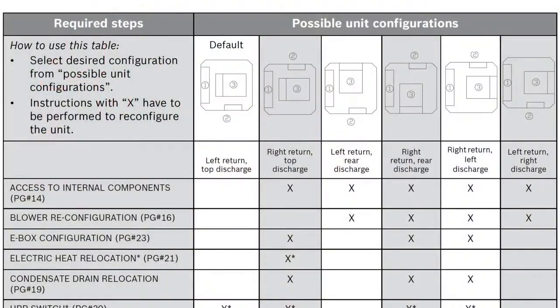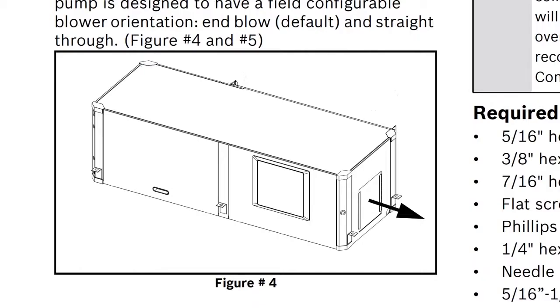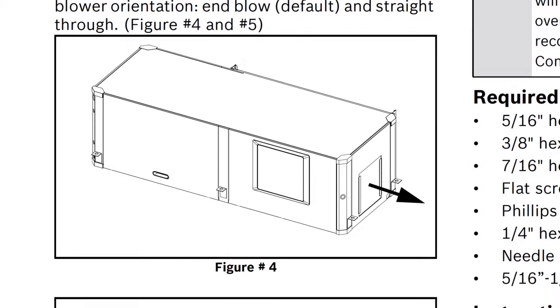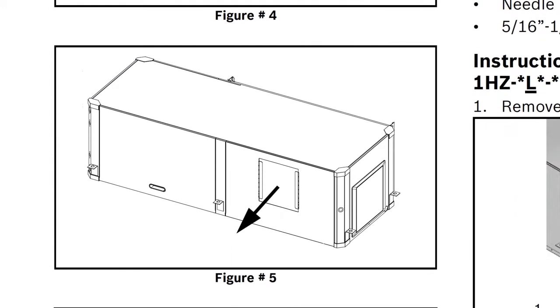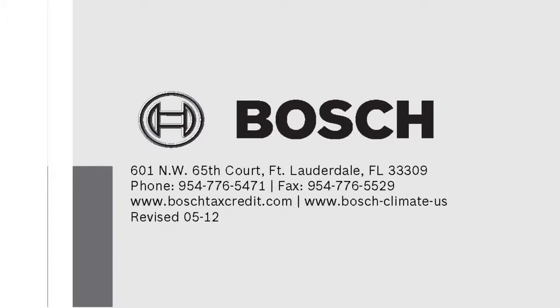When you have an application where a side or back supply air connection is needed and electric heat is required, you must use a duct heater installed in the supply air duct instead of internal electric heat. This also applies to the horizontal model when converting from end to side supply air connection. If internal electric heat is already installed from the factory, the electric heaters and electric heat E-box must be removed. Please call technical support in Fort Lauderdale to receive instructions for this process.